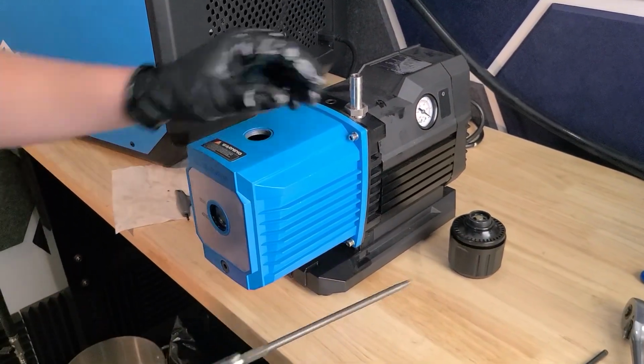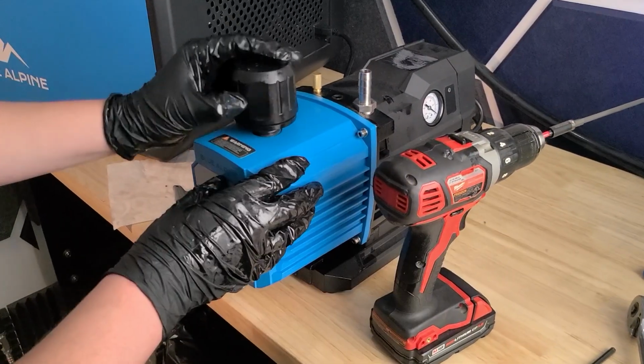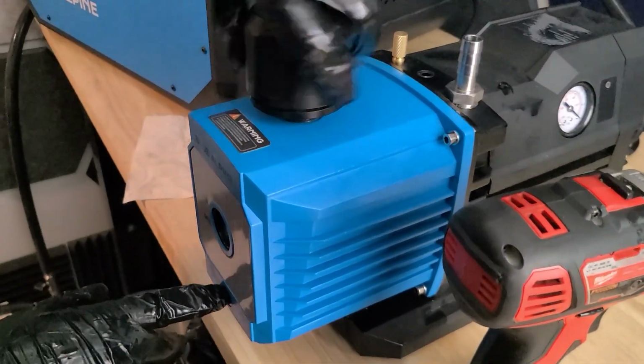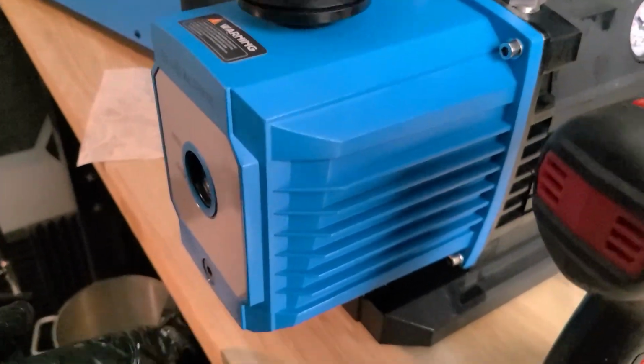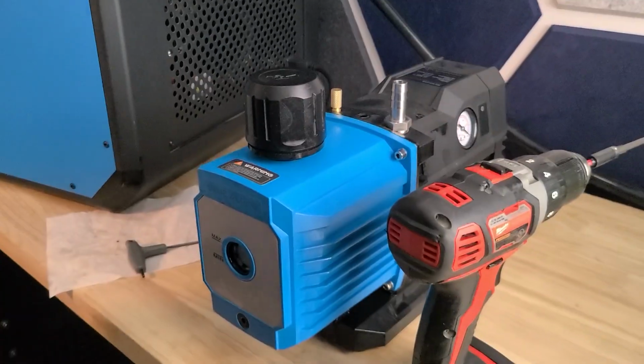Once the last screw is tightened down, you're going to want to take your filter, put your filter back on top. You're going to want to ensure that your drain plug is fully tightened, so when you add oil back into your pump, it is not going to leak, and you are ready to freeze dry again.